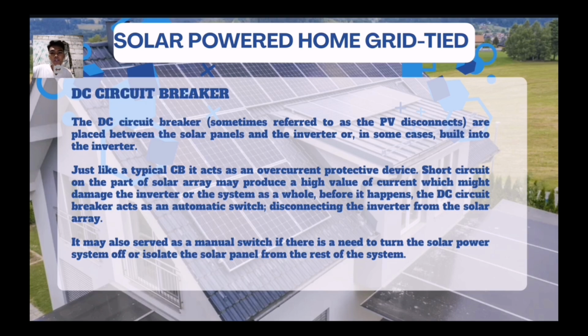A short circuit on part of the solar array may produce a high value of current which might damage the inverter or the system as a whole. Before it happens, the DC circuit breaker acts as an automatic switch disconnecting the inverter from the solar array. It may also serve as a manual switch if there is a need to turn the solar power system off or isolate the solar panel from the rest of the system.